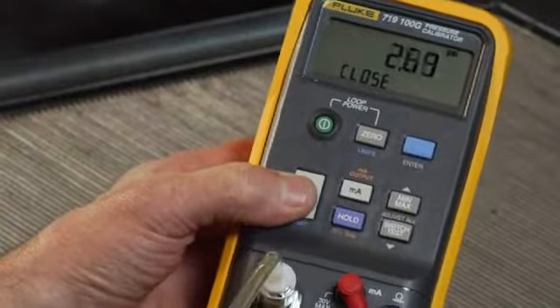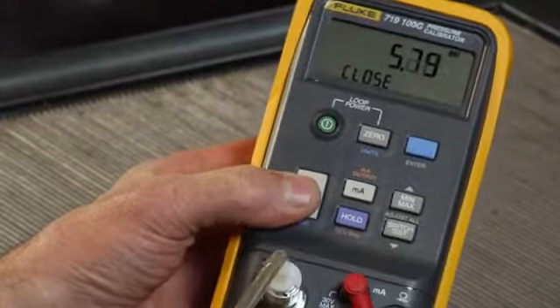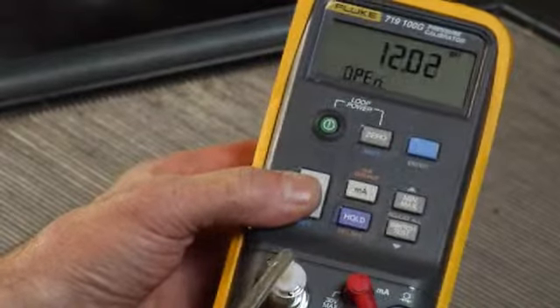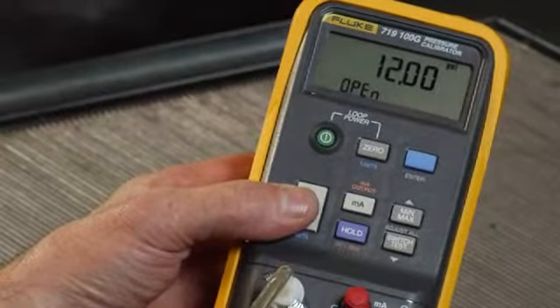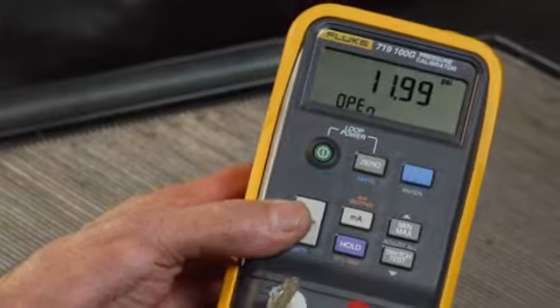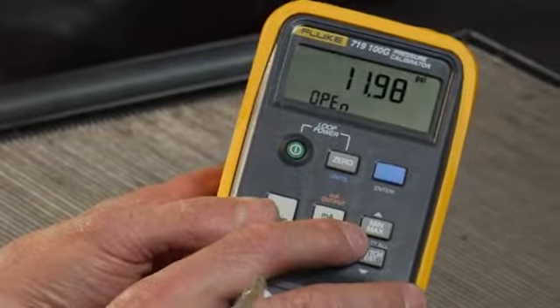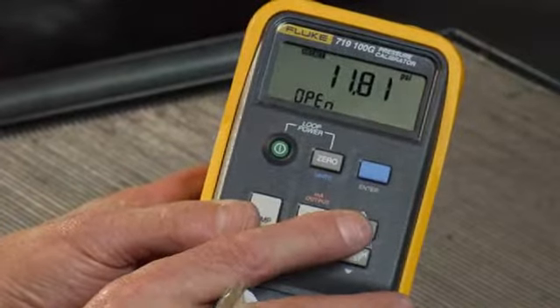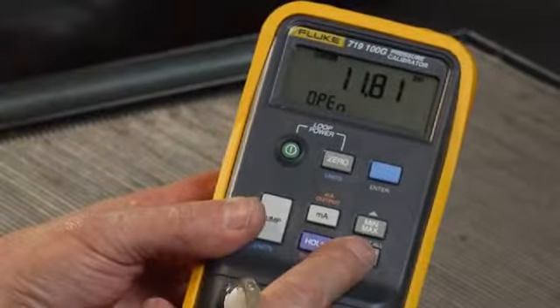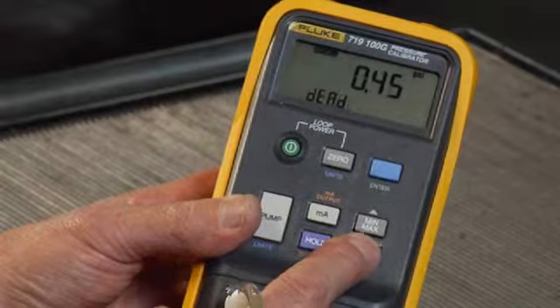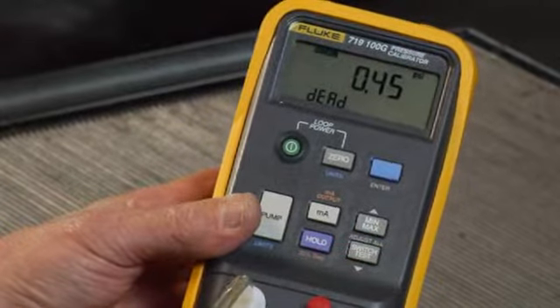Apply pressure to the switch with the electric pump and wait for the contacts to open. The contacts open, indicating a state change in the switch. Let the pressure out and wait for the contacts to close. The test is complete. Press Switch Test to recall where the contacts open, where the contacts close, and the size of the deadband for the switch.